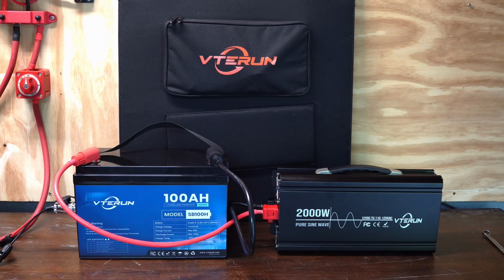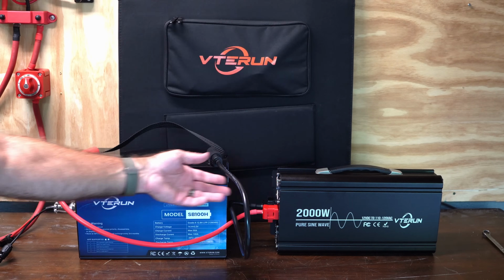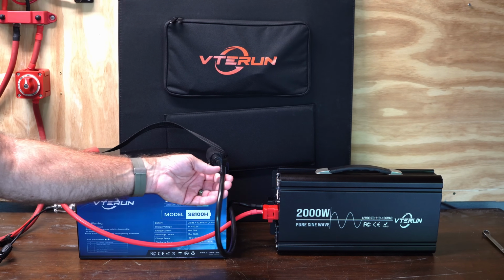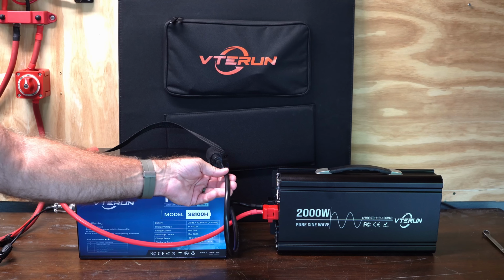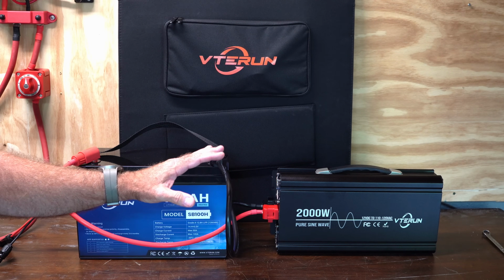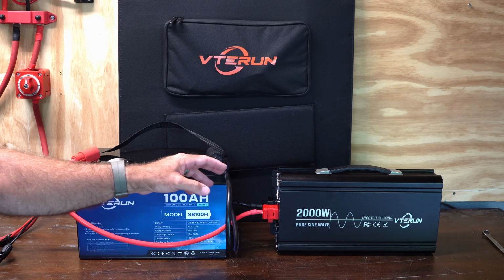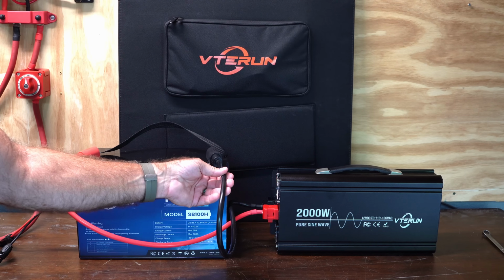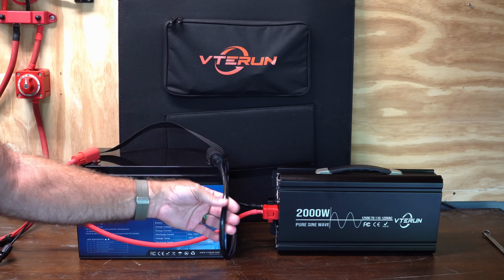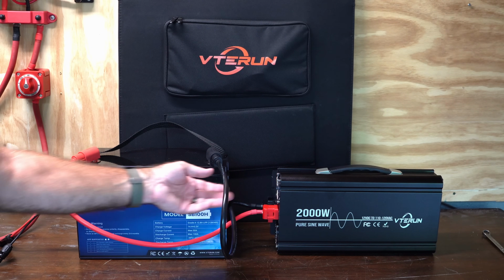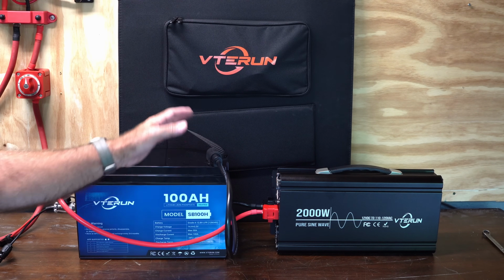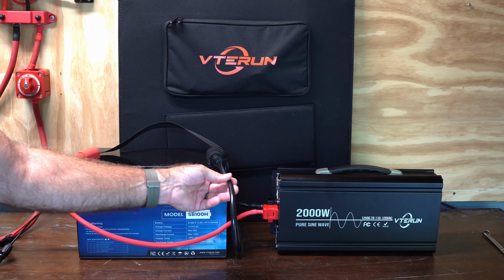I've got the AC inverter connected using these safety cables. This is nice because sometimes the problem isn't just the spark - the issue is that you could actually damage components in the inverter or even in the BMS with that sudden inrush of current. So this is just a nice, safer way to do this if you are connecting and disconnecting batteries with some regularity.